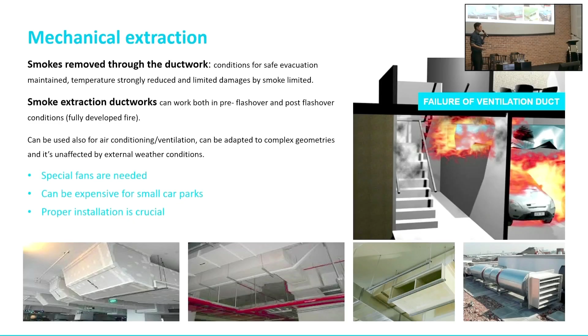So of course, if you go back to the data center, this circular issued by Bomba last year mentions two things - you need to fulfill MS 1780 and 1472, the criteria of smoke extraction and pressurization systems. When I go inside these two MS standards, they're very minimal. They mention about the material used to build your fire ducts or entire systems, they talk about the airflow, rain, all those things they covered, but they didn't actually say your duct needs to be fire rated.